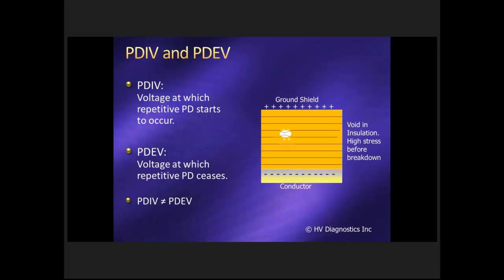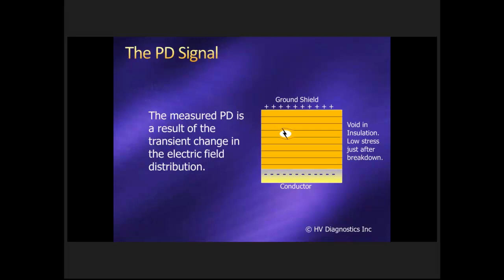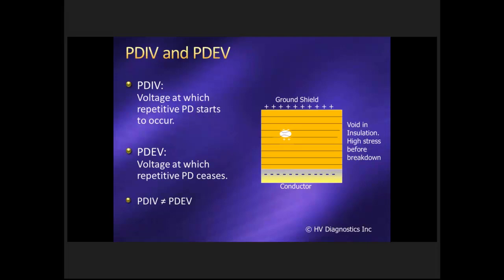And so if we look at the next slide, you can actually see that breakdown that's taking place, which actually neutralizes that tension inside the void for a short time. And so when that occurs, that transient that takes place is the measurement that we're looking at, is measuring that transient change in electric field distribution as the partial discharge takes place in the cable. Go back to the previous slide, the extinction voltage, which is the PDEV, that's the voltage, the applied voltage at which PD ceases. In other words, PD no longer takes place. And the inception voltage of PD is not equal to the PDEV. In other words, it tends to extinguish below the voltage in which it incepts. So if you, let's say, it incepts at about 20 kV on a cable, you may find extinction is about 16 kV, for example.